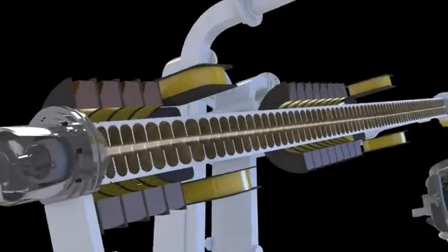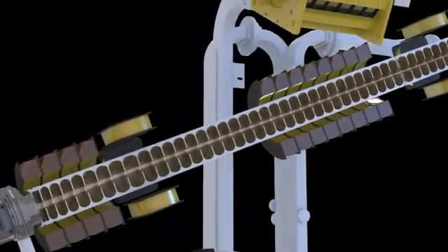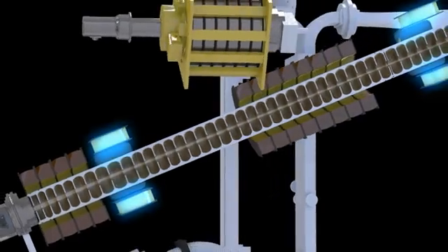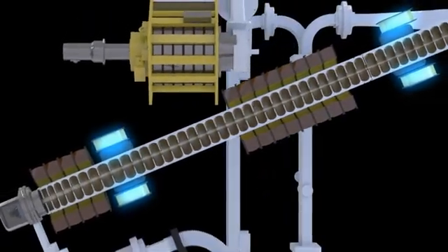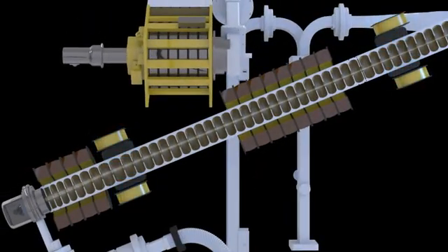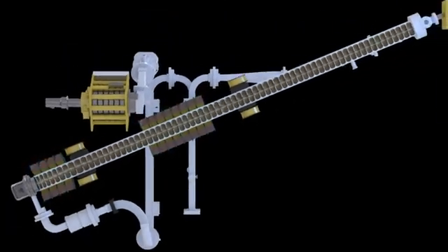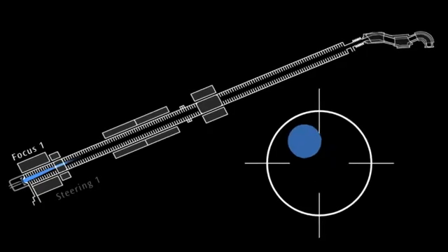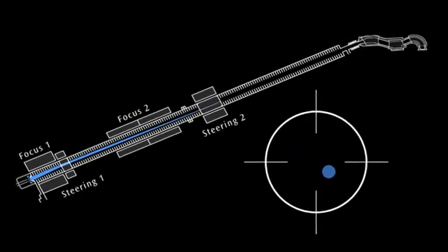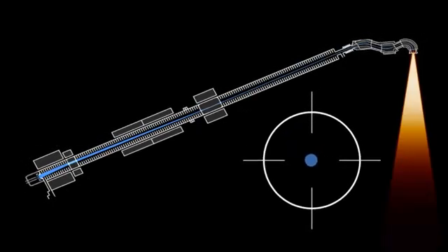The path of the negatively charged electron beam is controlled by two sets of quadrupole magnets, called steering coils, that surround the waveguide. An additional two sets of focusing coils help to further define the electron beam so that it is very fine, with a diameter similar to that of a pinhead, when it hits the target.